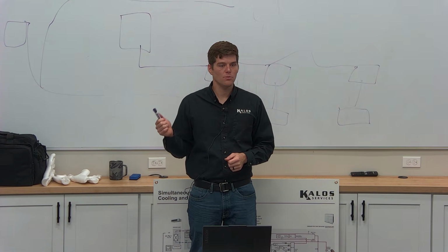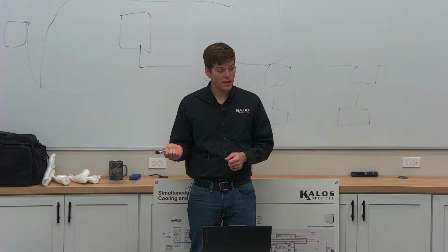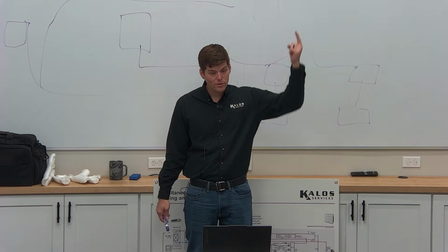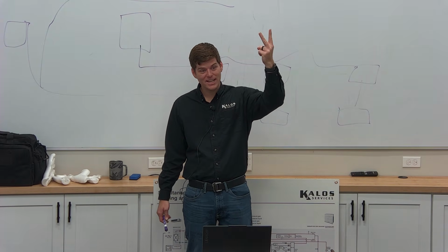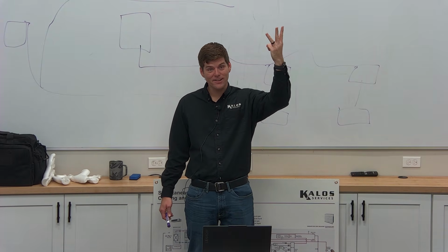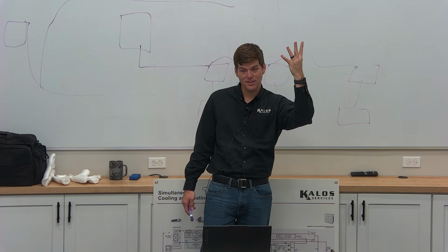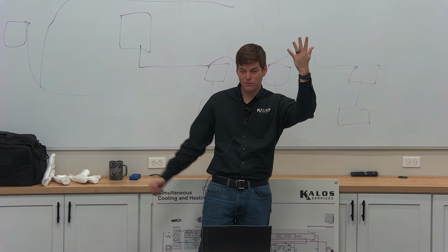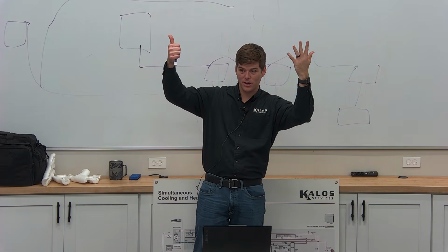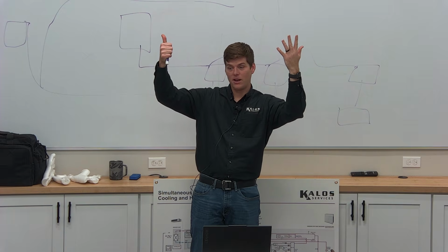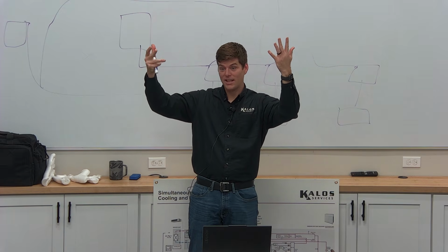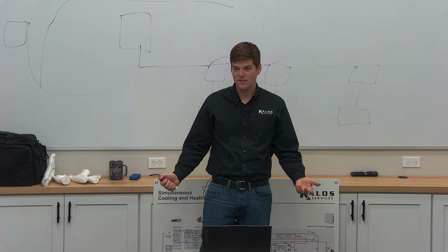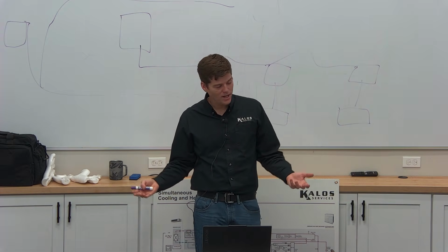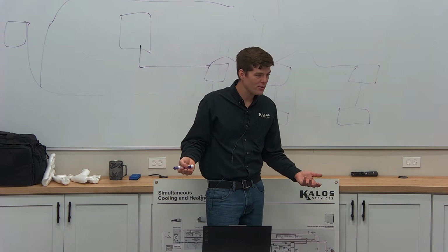24 volt control, we're limited by what? The number of wires we have, right? I have one for cooling. I have one for heating. I have one for a fan. I have one for electric heat. Lord forbid I have hot gas reheat. Lord forbid I have a solenoid valve on my liquid line that I have to close. Wait a minute, now I have more temperature sensors, and so it adds up. Are we going to run 20 wires to one indoor unit to the outdoor unit?